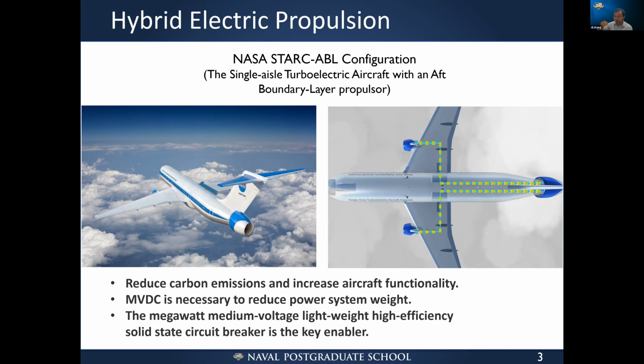If you have two MOVs, it's working already. Each of them is only 300 joule, right? It's less than 10% of the total power ratings in this specific design. If you use a circuit breaker to cut the regular current, let's say 1 kiloamp, not full current, just 1 kiloamp, the energy is even lower. So we have done some preliminary studies and didn't identify a huge risk there. So it's doable. Okay, all right, thank you.